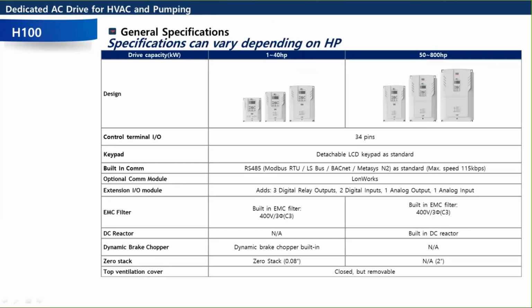We do have that zero stack capability. What that is, that's the side-by-side mounting. So you can mount them 2 millimeters side by side up to 40 horsepower. And then the bigger guys, once you go 50 horsepower and up, then it's 2 inches side by side.